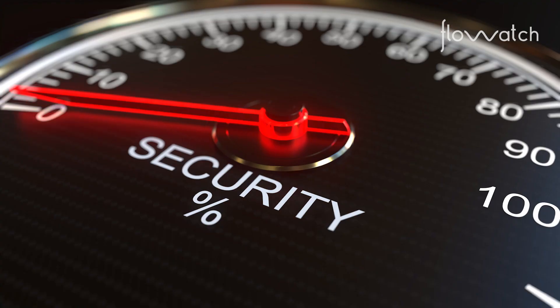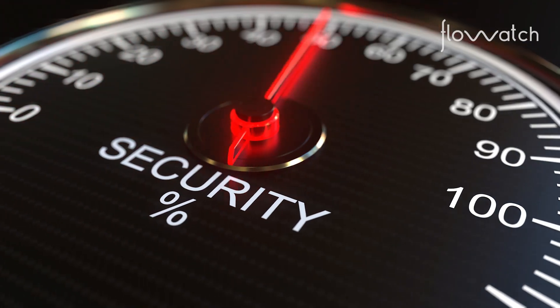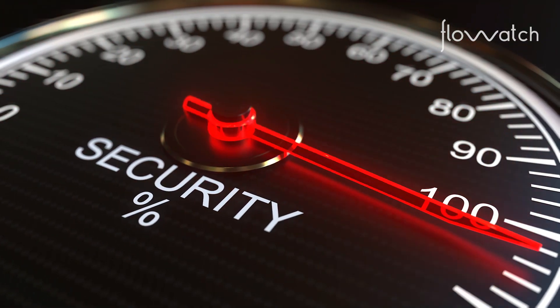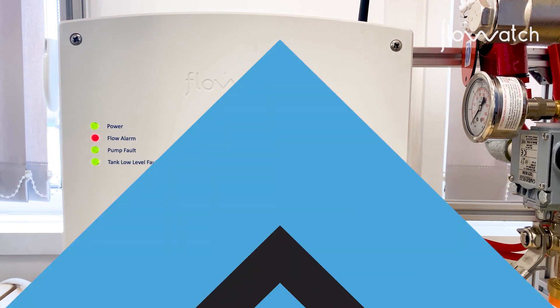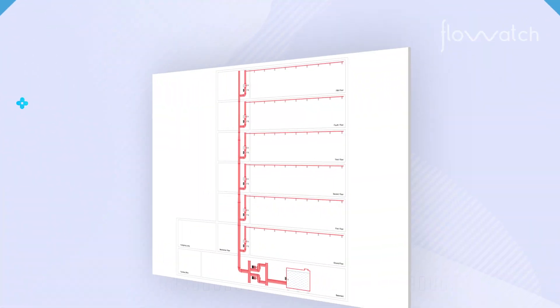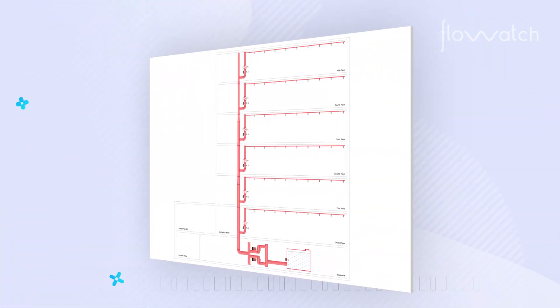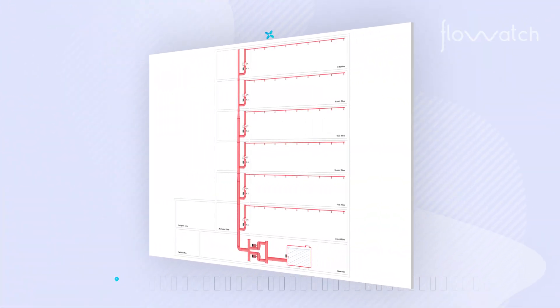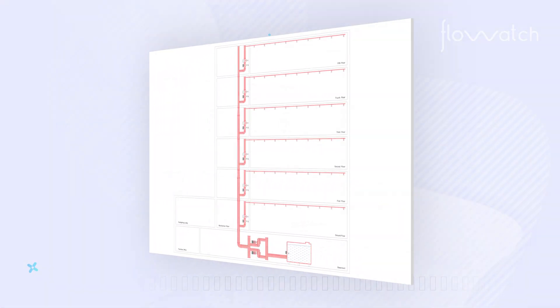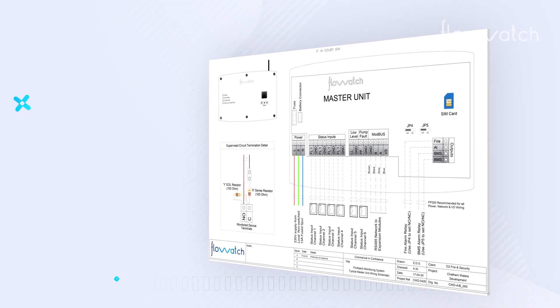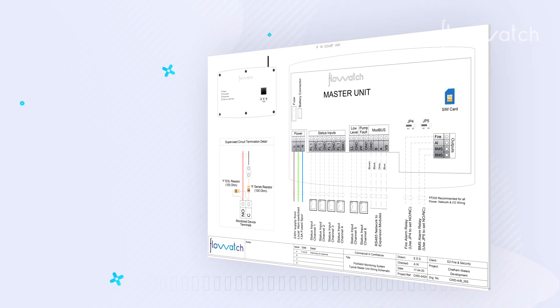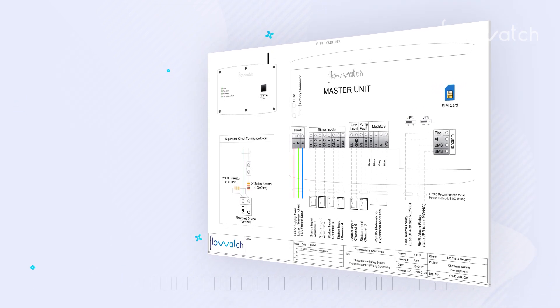Flow switch detection is otherwise known as an A alarm. To connect either a flow switch or monitored isolation valve, a two-core FP 200 1 millimeter cable should be installed from the master unit and connected to the common and normally open contact of the field device.